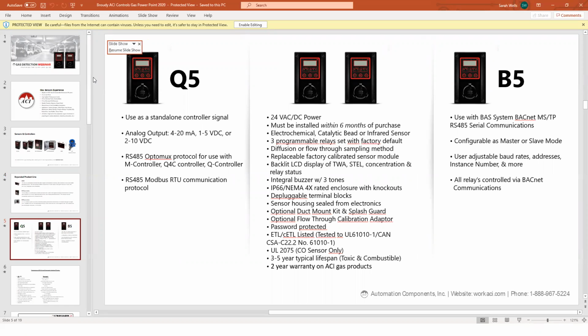Okay, Q5, B5. Basically here are the two differences. The Q5, you can use as a standalone controller signal. It comes with 3 relays, 4 to 20, LCD, digital communication. You'd have to have a controller for that. But if you just want a standalone, going back to a fan, either via 4 to 20 or the relays, that would be good for that. The B5, of course, is the BACnet version of that. Same features, 3 relays, LCD, horn buzzer, all of those features on that.